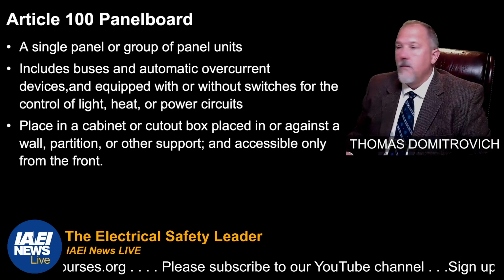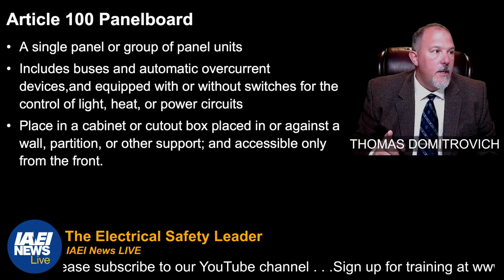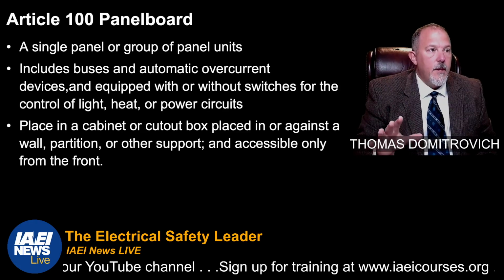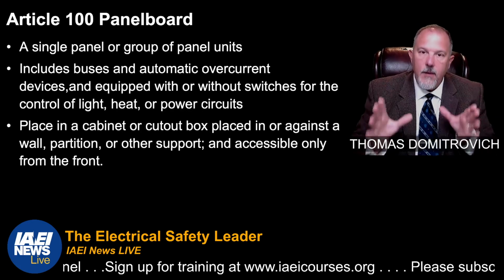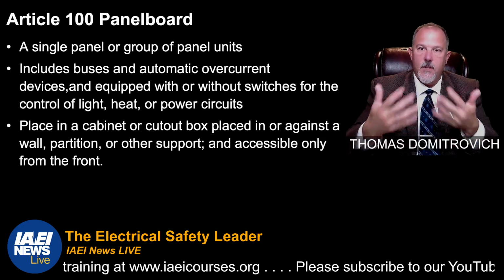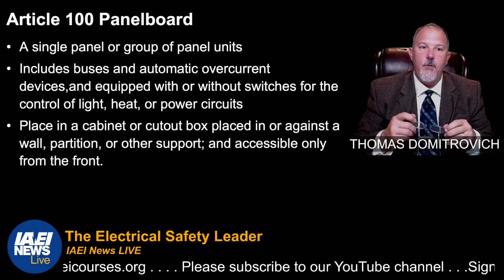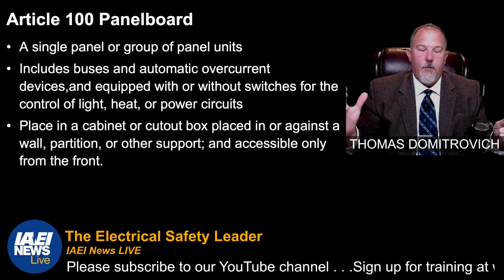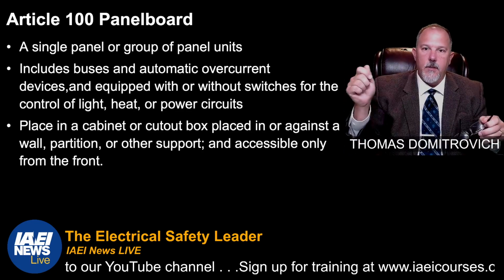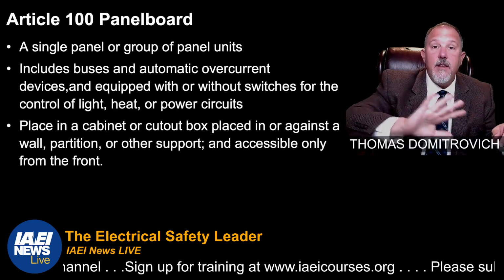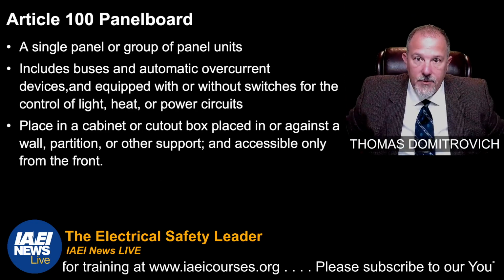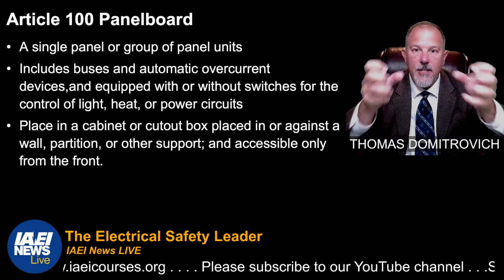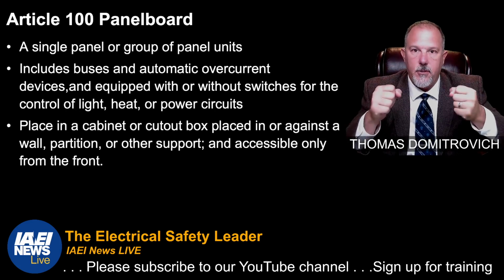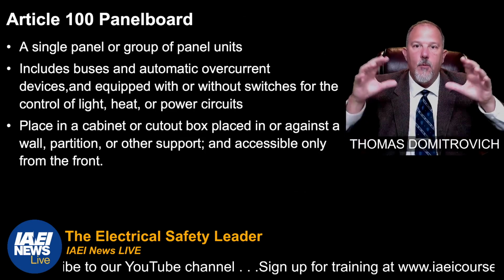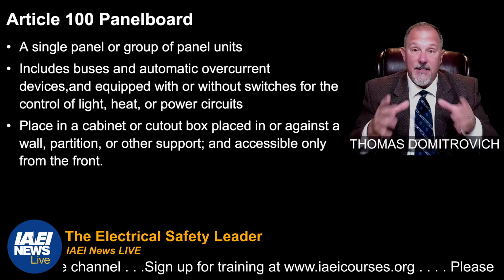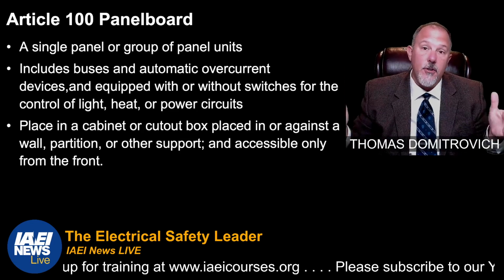Okay, so first change in panelboard. In the definition, you have to remember that when you say the word panel, this is a premise. Here's just from me to you, an easy way to think about this. When you look at that box on the wall that has the door and all that good stuff, take the door. If you take the door off, if you take the dead front off, if you disconnect all of the wires, and then you unbolt the internal guts of that enclosure, what you mount the breakers on, what you put your fusible switches on, that is the panel board. The panel board is not the enclosure included.